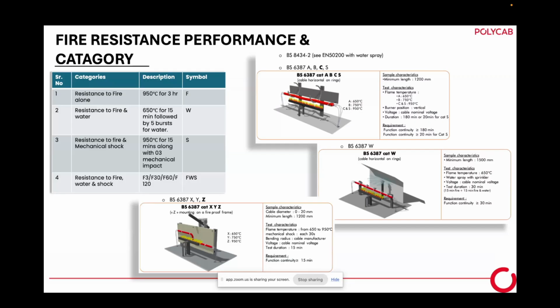On the right side, you can see the fire testing arrangement. There is a burner which can develop temperature up to 1000 degrees, and over that there is a cable connected to a circuit. When the burner starts, this cable is connected to a load with a 1 kV supply, and a light will be glowing. The moment it gets short-circuited, that light will go off.